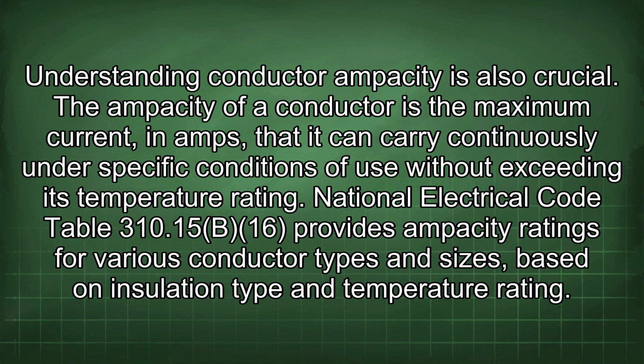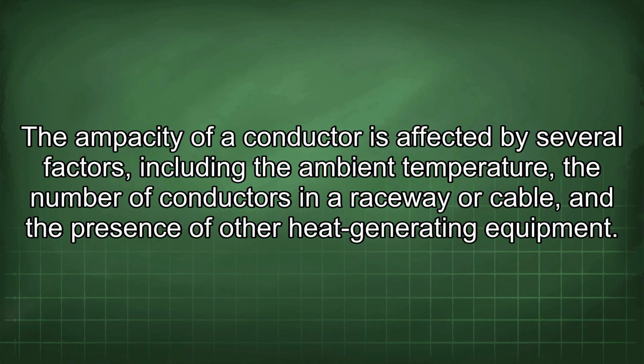Understanding conductor ampacity is also crucial. The ampacity of a conductor is the maximum current, in amps, that it can carry continuously under specific conditions of use without exceeding its temperature rating. National Electrical Code Table 310.15(B)(16) provides ampacity ratings for various conductor types and sizes, based on insulation type and temperature rating. The ampacity of a conductor is affected by several factors, including the ambient temperature, the number of conductors in a raceway or cable, and the presence of other heat-generating equipment.